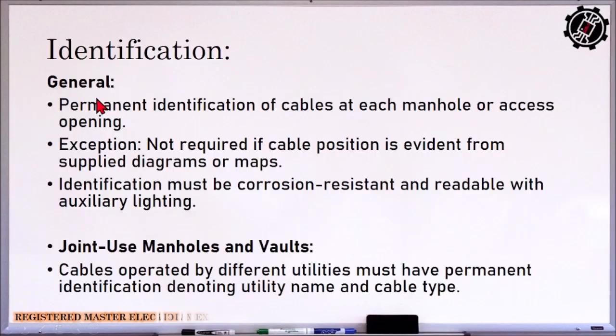Okay, so the identification. How are we going to identify which of our cables is the communication cable and which is the supply cable? So, permanent identification of cables at each manhole or access opening. Permanent means it cannot be removed. Exception: not required if cable position is evident from the supply diagrams or maps. So if there is a consistent diagram of the actual arrangement of our cables, there is no need to add identification.